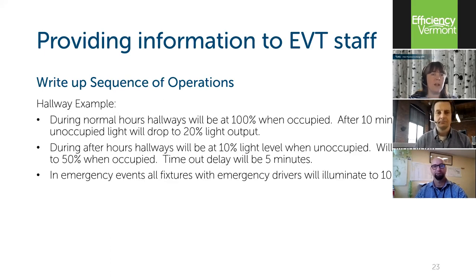Here's an example written out space by space. This is the hallway, how it runs during normal hours: it's on 100% when occupied, and after 10 minutes it drops to 20% light output, so it's never dark going down those halls. During after hours, it stays at 10% when unoccupied, but if someone comes in it only goes up to 50%, on a 5-minute delay. The emergency lights, during an emergency event, go all the way up to 100%.